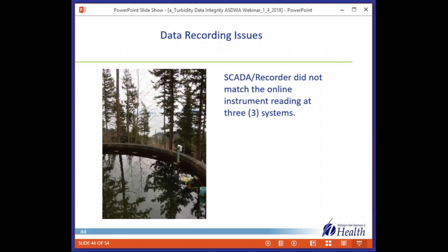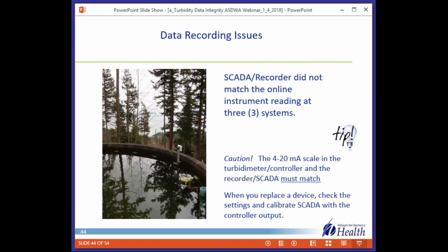So we did encounter, infrequently, a few data recording issues. At 3 systems, the SCADA or the recorder did not match the online instrument reading. Keep in mind that the scale that you set in the controller has to match the scale of the recorder in SCADA. So when you replace a device or change settings, you need to calibrate SCADA with the controller output.